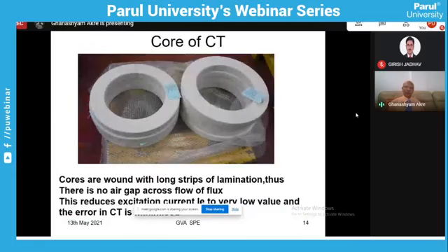I have told you that these cores of these current transformers are not rectangular type which we have seen. It is round or toroidal fashion. Why toroidal? You see, the excitation current which is drawn by any magnetic circuit will be utilized for flowing the magnetic flux inside the core. You have seen in the power transformers or distribution transformer laminations, they are actually set one by one. That means there are air gaps appearing at the joint. So every lamination will have their joints, and many joints will be there. There will be air gap, and this air gap is resistive. This will not allow the flux to pass very easily. So that means its reluctance will be more. So in that case, what happens?